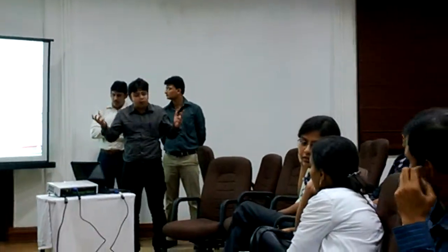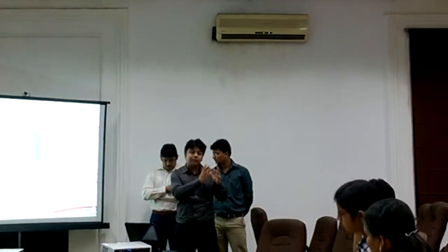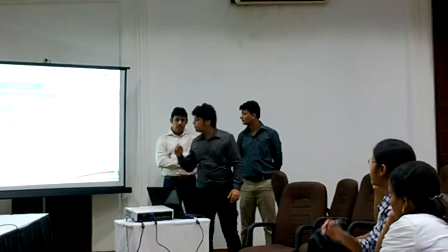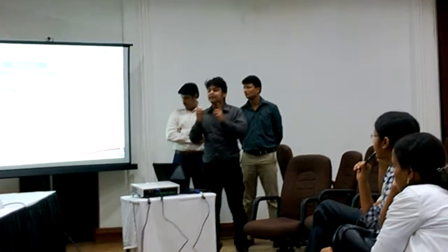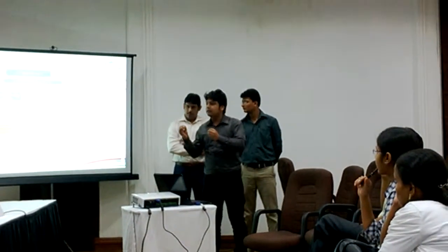Oxidizer takes the solvent which is produced during the entire coating process and burns those solvents. Moreover, during the burning, an enormous amount of heat is produced and we effectively use that heat throughout the other processes of the line. Now coming down to my problem, the first case was that the oxidizer was tripping frequently during startup. Why was it tripping? We have used two flame scanners, where the feedback of the flame scanner in terms of voltage comes to our burner control unit, and that voltage went missing a lot of the time.